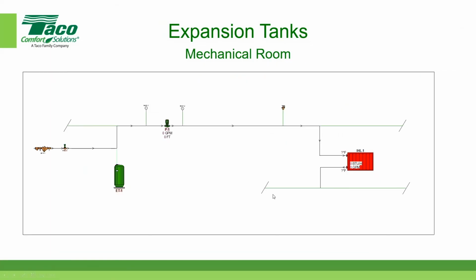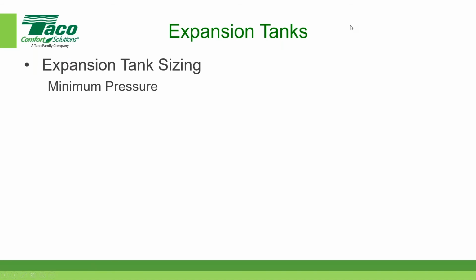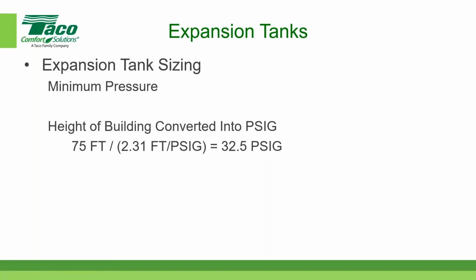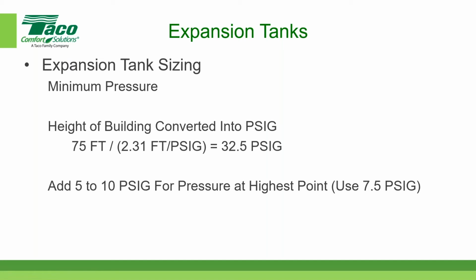In our mechanical room, this is what our piping is going to look like. We're going to have an air handling unit down there, expansion tank, our pump, fill station. In a minute, we're going to talk about the minimum pressure that we need at the bottom of the building, and we actually just calculated that. The minimum pressure is the height of the building converted into pounds per square inch gauge. In our case, 75 feet divided by 2.31 feet per PSIG equals 32.5 pounds. We want somewhere between 5 and 10 pounds at the top of the building, and for today's example, I wanted simple arithmetic, so I chose 7.5 pounds, halfway between 5 and 10.